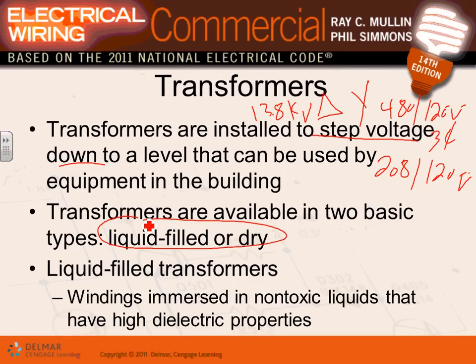So what they do is either they have paper and so on to isolate them, or they have some type of liquid that they immerse both the primary and the secondary in, and that liquid will act as an isolator. It isolates them from each other so they can't short, and it acts as a coolant. It helps cool this equipment. The immersion liquids are non-toxic, of course. You don't want to have toxic liquids. They are high dielectric components, highly insulating. So it acts as a cooling mechanism as well as an isolating mechanism for the coils.